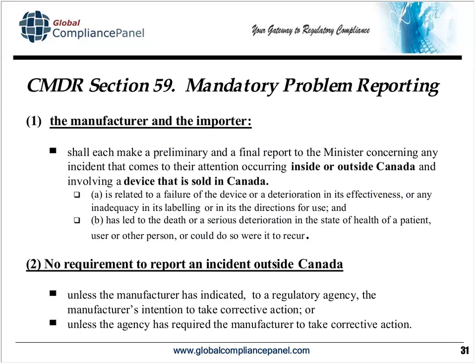Regarding mandatory problem reporting, that's under CMDR Section 59. The manufacturer and importer requirements are stated here. Please note that there is no requirement to report an incident outside Canada. Exception applies. What if an incident happens in the US? Well, that's clearly outside of Canada. What if you have taken some action with the FDA, or if FDA requests some information from you? If that is the case, you are still required to report in Canada.